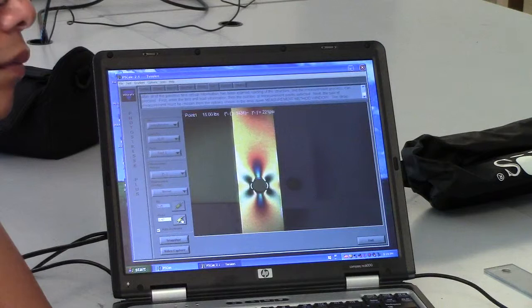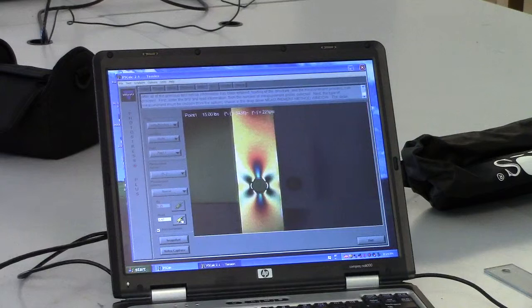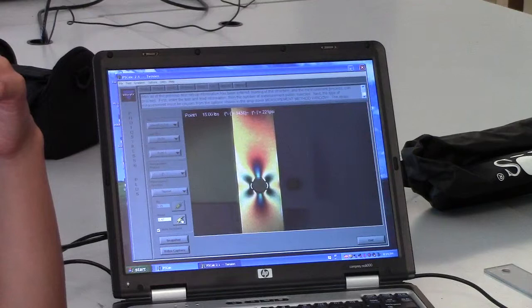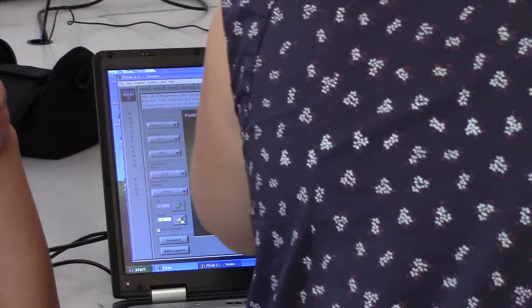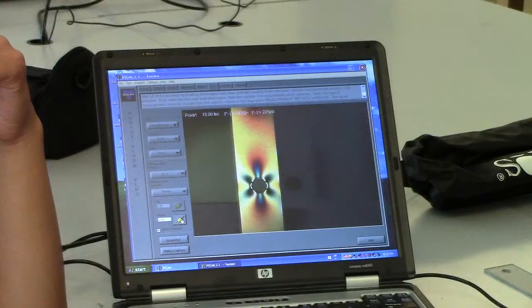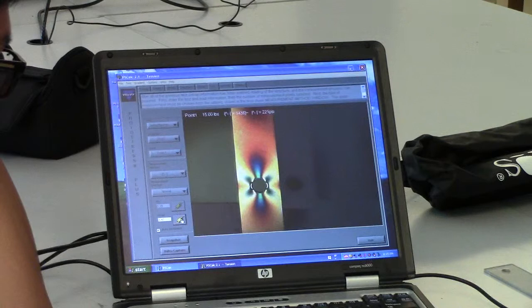Isn't it so subjective? It is. I can just do a little bit more and say, oh, this is the point. But one thing to make you feel a little better: these numbers on the compensator change fairly slowly, so you have some wiggle room. You're right, you're concentrating on the point, but around it is changing a lot. It can just confuse you. We want to see that black converge on that point. I actually think it's pretty good where you have it. Yeah, let's go with that.